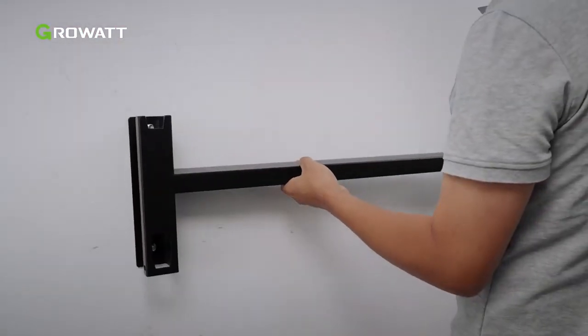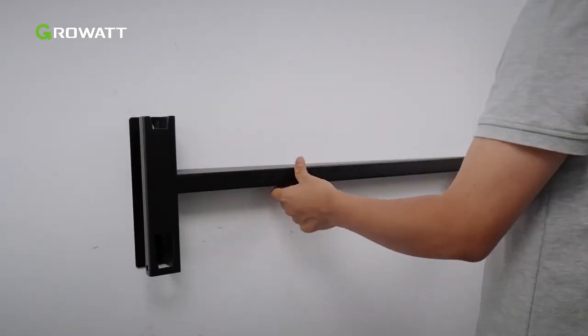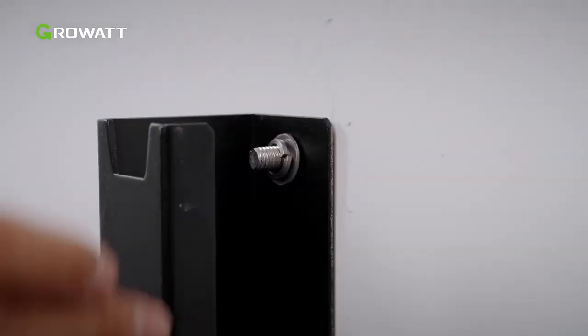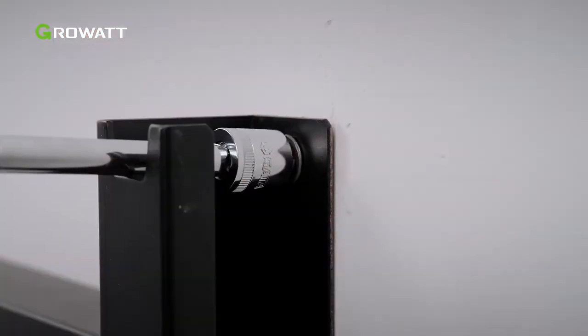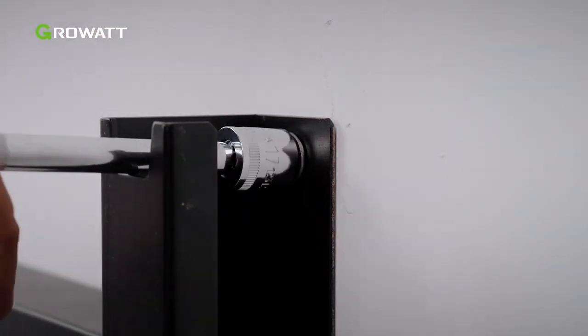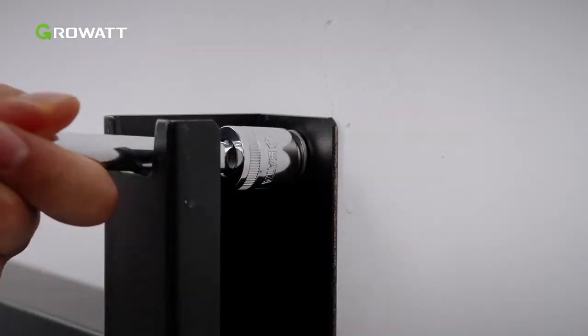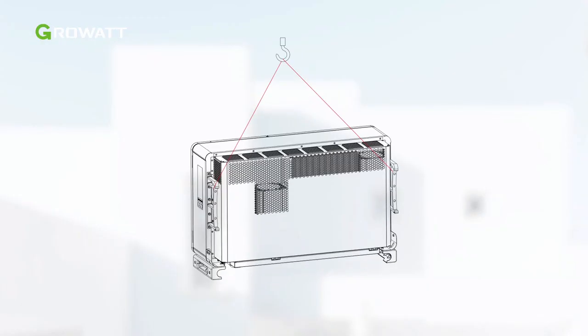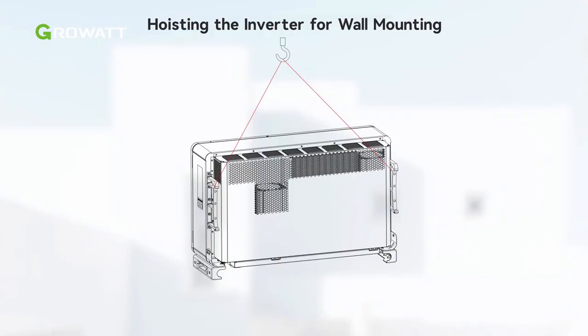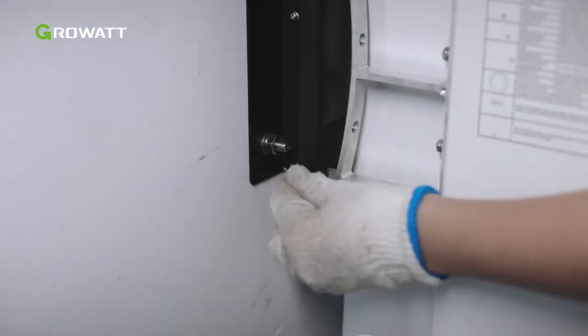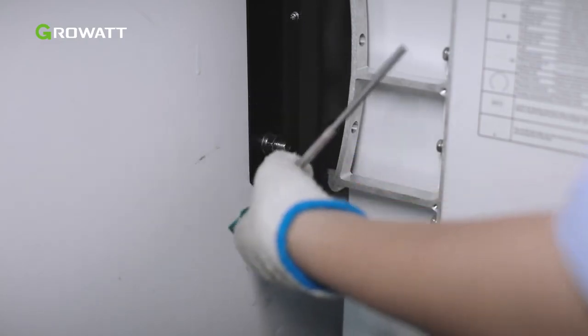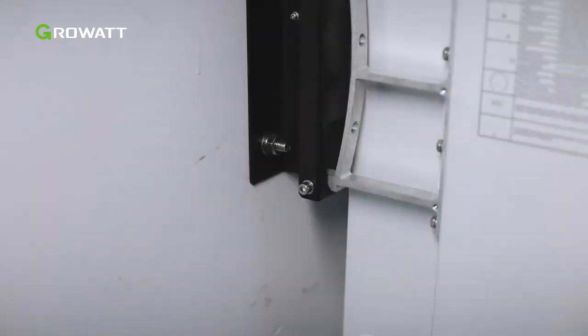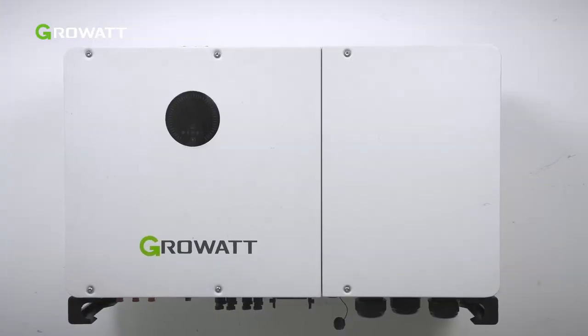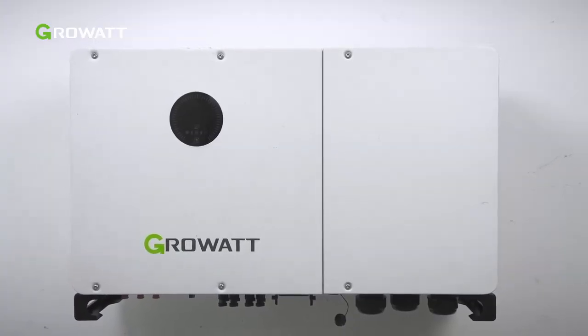Hang the wall mount bracket on the expansion screws. Tighten the bolts to attach the wall mount bracket onto the wall. Ensure the bracket has been firmly installed before mounting the inverter onto it. It is recommended to hang the inverter with a rope for wall mounting. Please ensure the rope is strong enough to carry the weight of the inverter. After mounting the inverter onto the wall mount bracket, install the bolts and tighten them. Please check if the inverter has been properly mounted and tighten all screws after wall mounting.